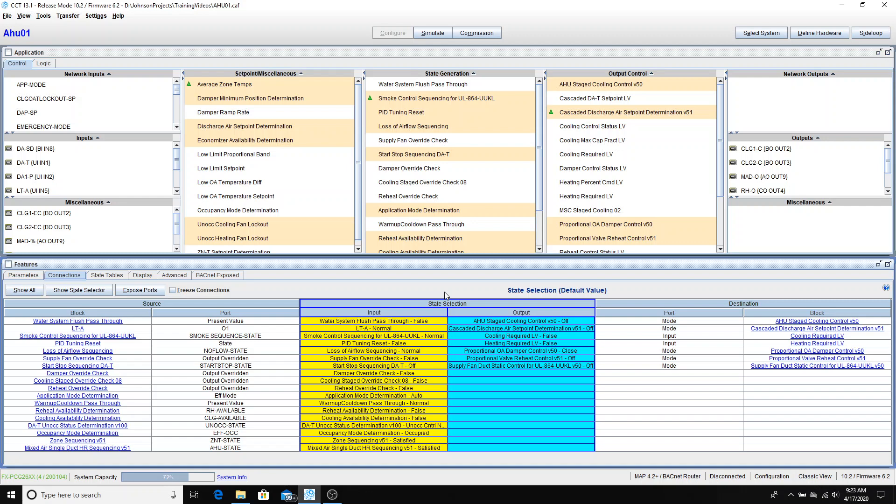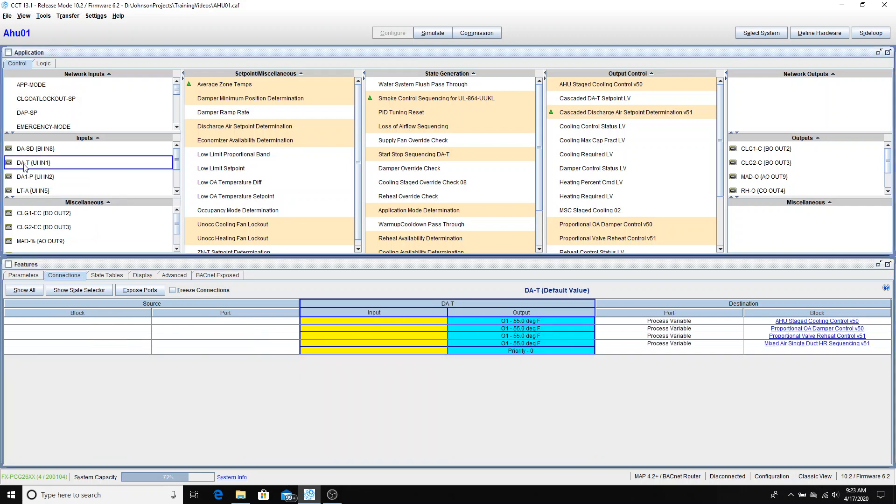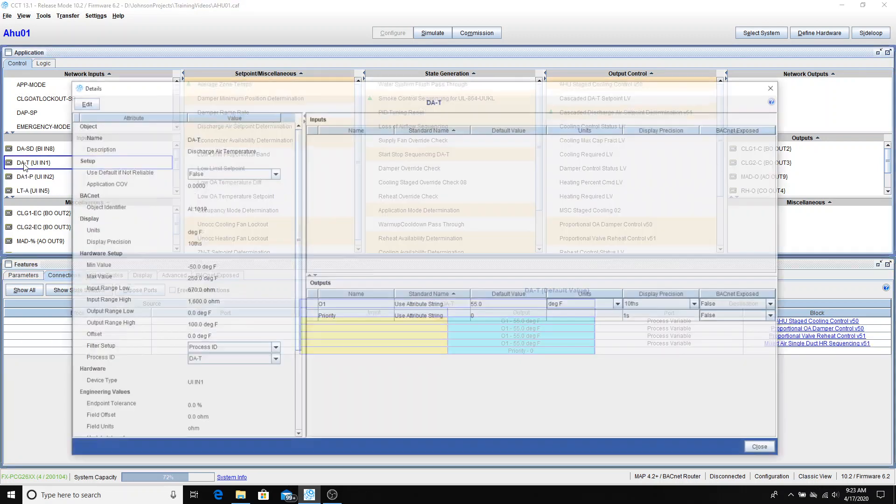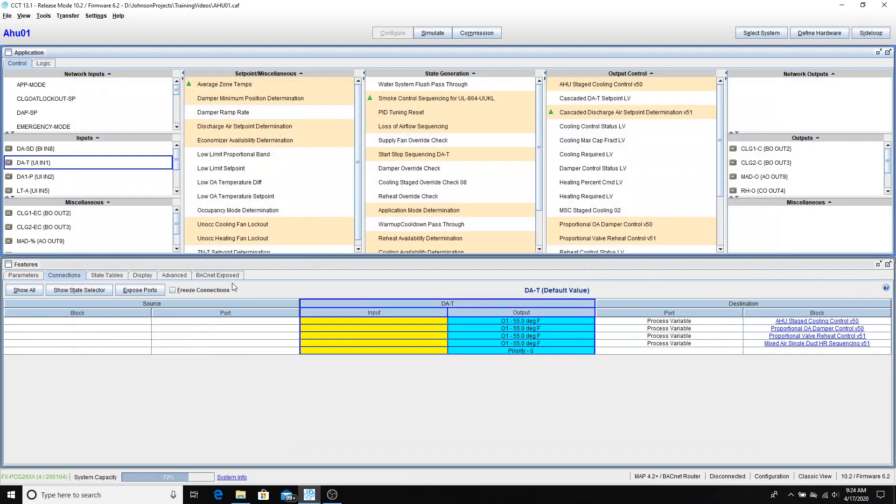Before we move on to the question and answer for the VAV boxes, we'll need one bit of information for peer-to-peer. We're going to be sharing the discharge air temperature with the VAV boxes so that they know when to go into morning warm-up mode. So we'll go up to discharge air temperature DA-T, double click, and our object identifier for BACnet is analog input 1019. So we will make note of that and then move on to creating the VAV boxes.